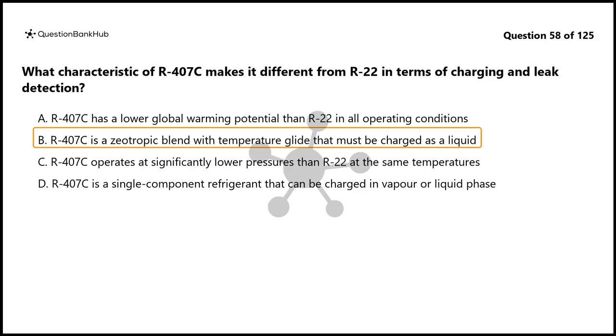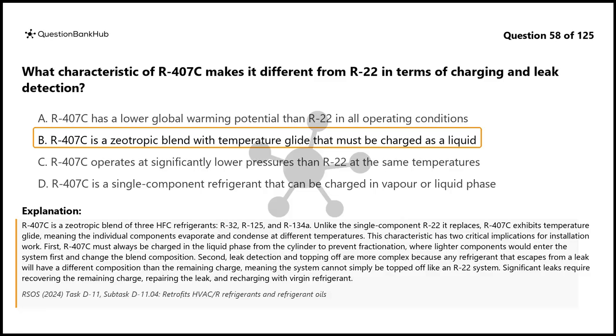The correct answer is B. R407C is a zeotropic blend of 3 HFC refrigerants, R32, R125, and R134a. Unlike the single component R22 it replaces, R407C exhibits temperature glide, meaning the individual components evaporate and condense at different temperatures. This characteristic has two critical implications for installation work. First, R407C must always be charged in the liquid phase from the cylinder to prevent fractionation, where lighter components would enter the system first and change the blend composition.